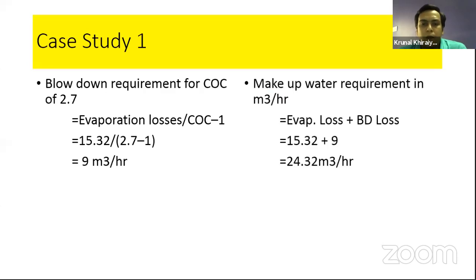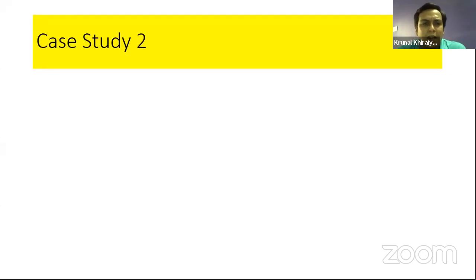Makeup water required means evaporation losses plus the blowdown losses. If you go with the mass balance equation, whatever masses come out of the cooling tower, the water we supply to the cooling tower is our M in, and whatever goes out is M out, and we need to balance it. So blowdown losses also come out, and evaporation loss is also going out in the form of water vapor. So the total water loss is equal to the evaporation losses plus blowdown losses. So every time we need a makeup water supply equal to evaporation losses plus blowdown losses. So we need to supply 24.32 meter cube of water every hour. Then case study 2.